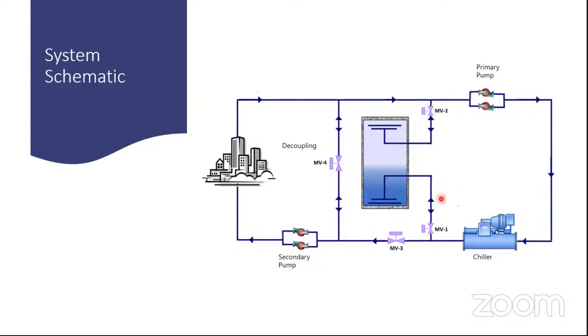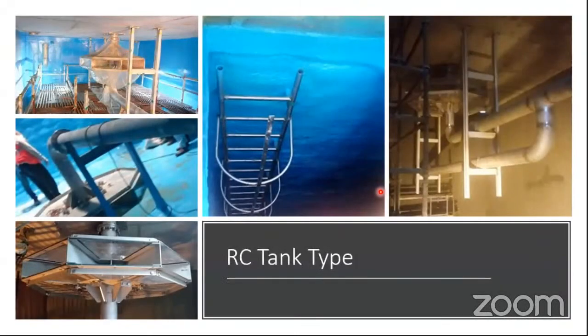So that's charging happening. For example, if our chiller is of 1,000 ton capacity and our load is currently 700 tons, so if it is delivering 1,000 tons, 700 tons could be sent here and the balance 300 tons could be sent here for charging the thermal storage tank at the same time. So this is about all the possible modes of operation in this kind of a schematic, wherein the idea is demand management.